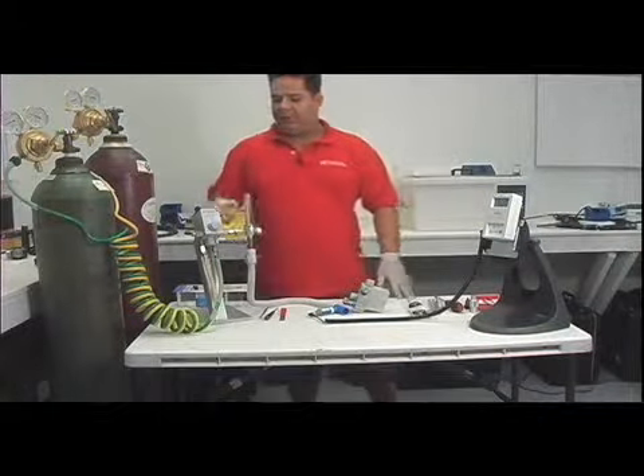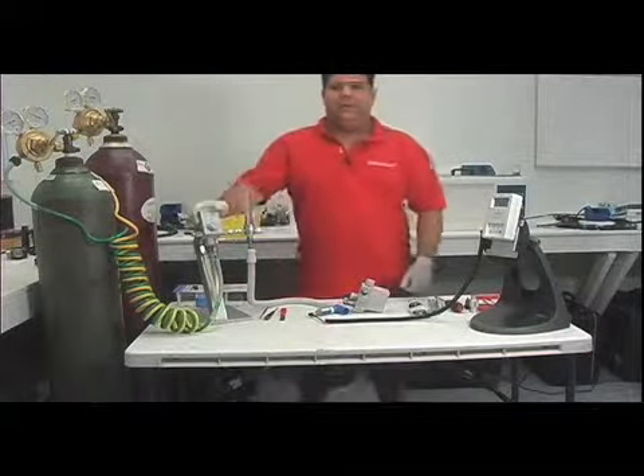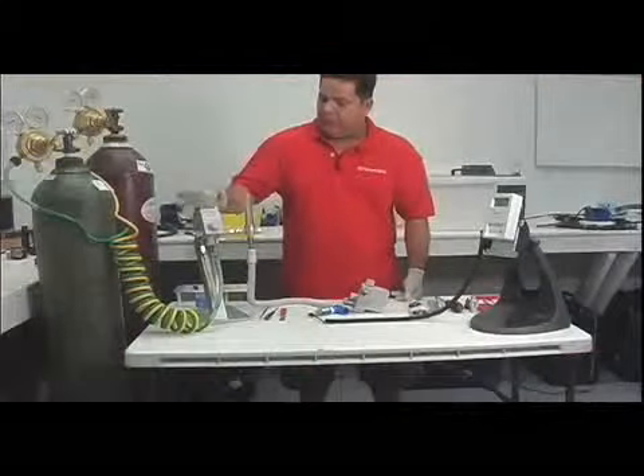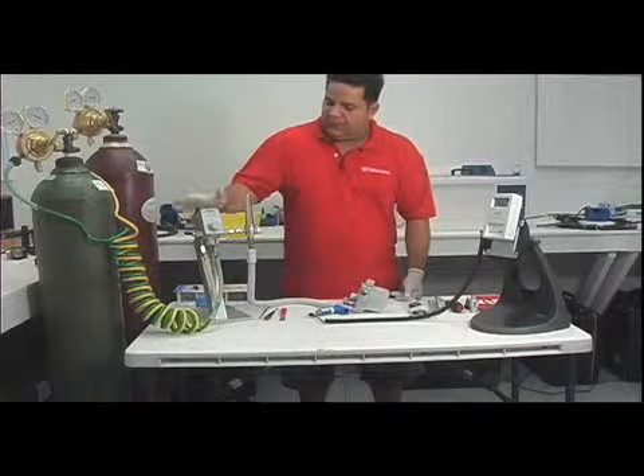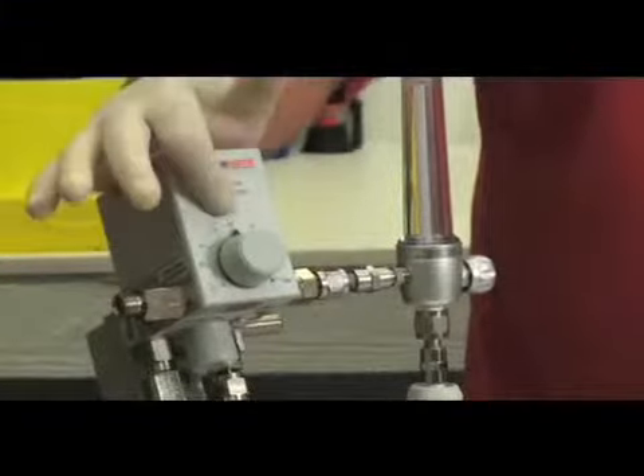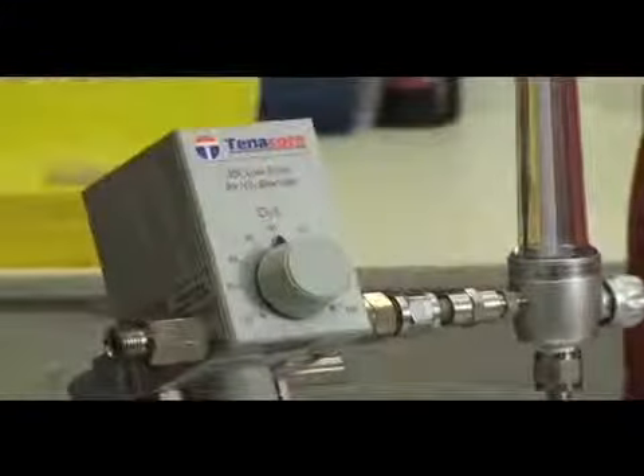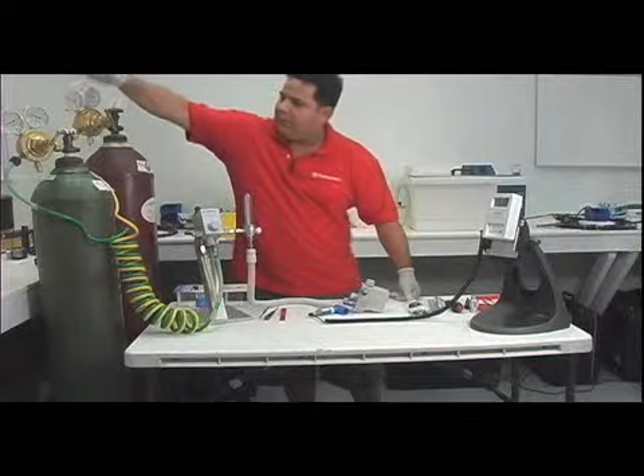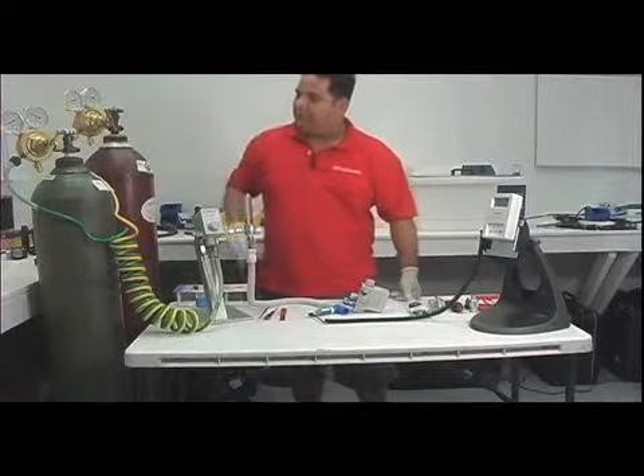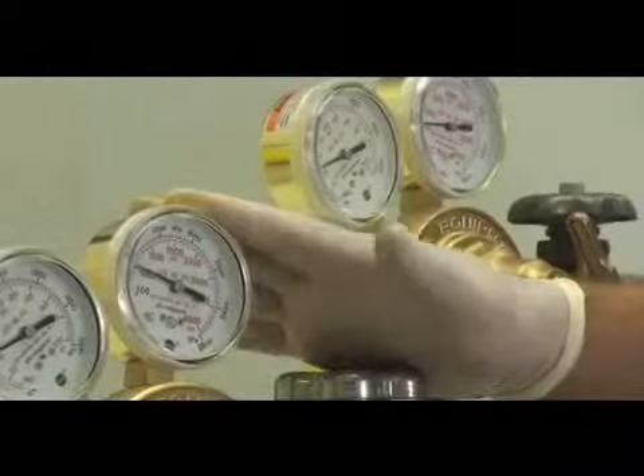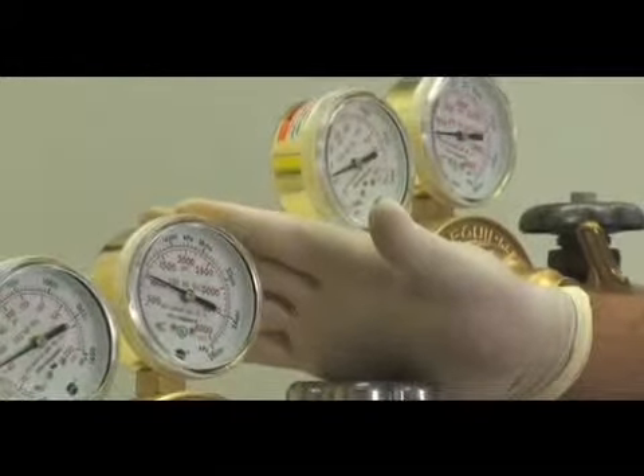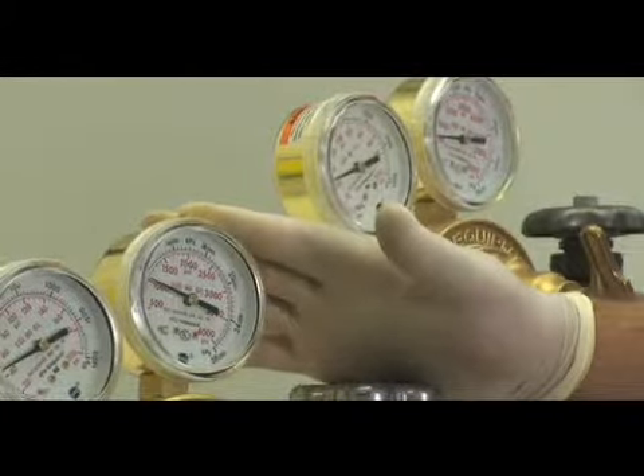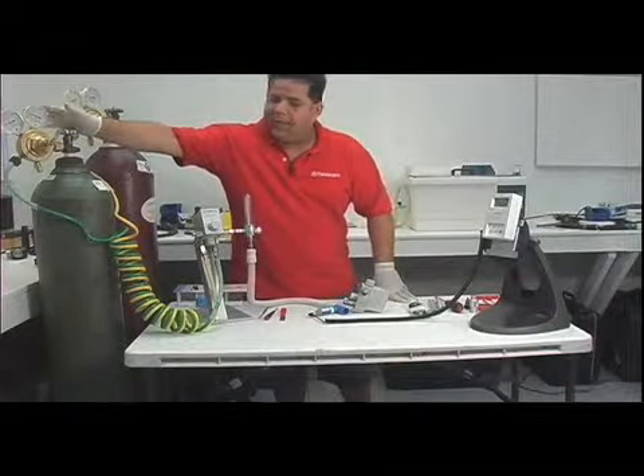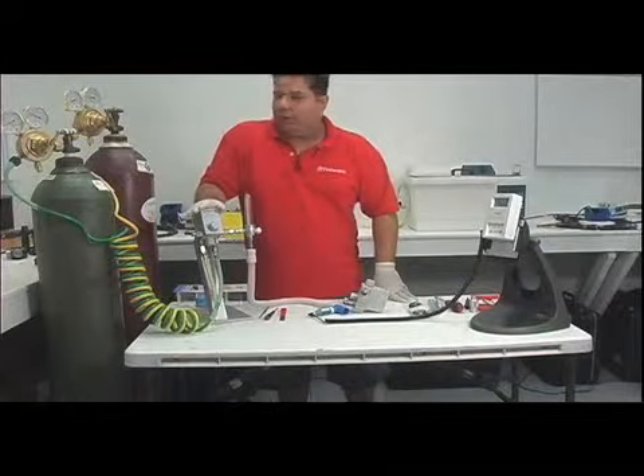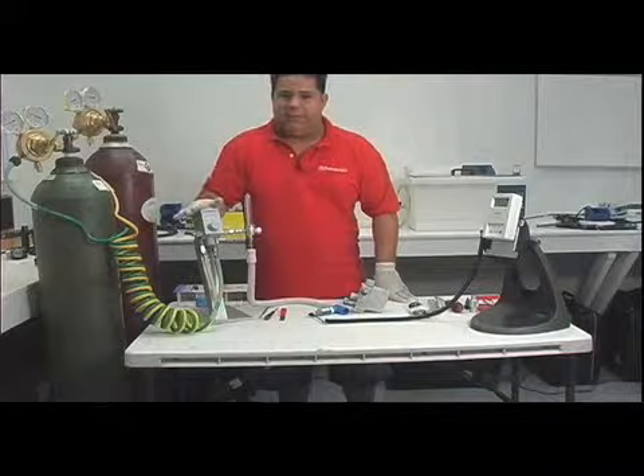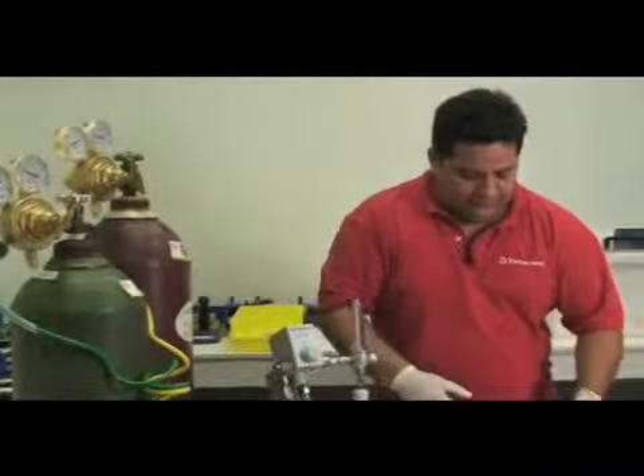Now that we finished the calibration, we're going to proceed to do the final part of this procedure, and we're going to calibrate the alarm. In this case, we need to be on a 60% concentration of oxygen. We need to have 50 psi on both regulators, and what we're going to do is we're going to lower one end down to 30 psi to create a 20 psi difference between the two lines, and that should make the alarm go off. The way to calibrate it properly is on either side.